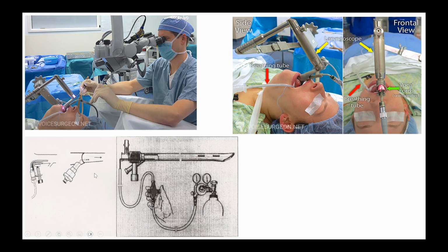And this is the picture of a Sanders jet ventilator. You can see this is the high pressure oxygen delivery tube, and this is the control mechanism. And another high pressure tube goes into a small nozzle being delivered at the proximal end of the rigid laryngoscope, the surgeon's end. And once the oxygen gets delivered here, it will entrain atmospheric air from the outside and deliver a higher volume but reduced oxygen concentration. So this is how the jet ventilator works.